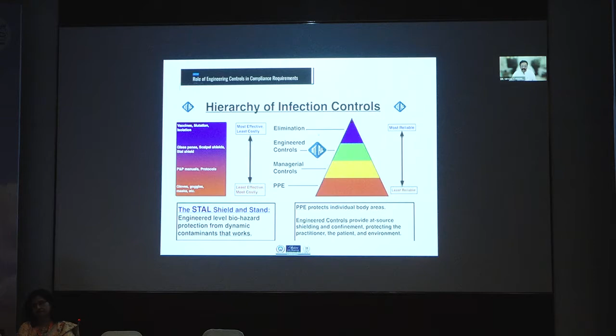Basically, air is used as a disinfection as well as dilution medium through effective use of ventilation, diluting infection and improving air quality by filtration. You reduce exposure time to infection by having a pressure differential or positive pressure. By using optimum temperature and humidity, you also reduce the growth of microbial flora inside the operation theatre. And by adding ultraviolet treatment to the HVAC, you reduce the viability of organisms.